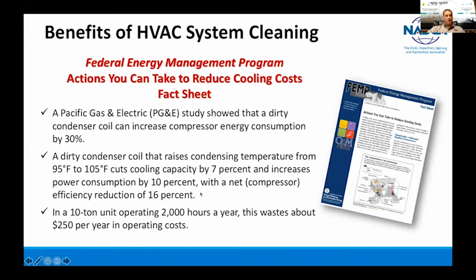It's just working so much harder. In a 10 ton unit operating 2000 hours a year, this wastes about $250 per year in operating costs. I mean, that becomes quite significant if these things can just be taken care of on a normal maintenance program for cleaning.